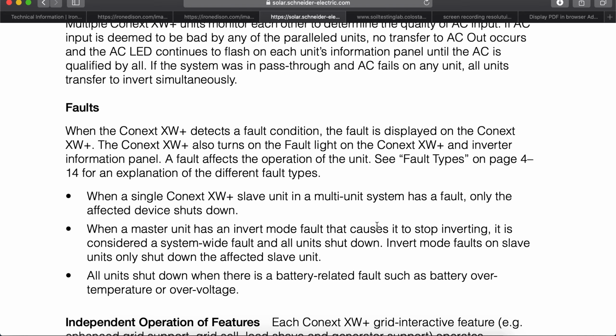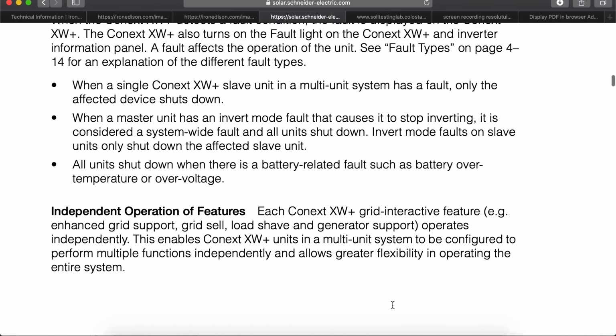When a single Conext XW Plus unit in a multi-unit system has a fault, only the affected device shuts down. When a master or leader unit has an invert mode fault that causes it to stop inverting, it is considered a system-wide fault and all units shut down. Invert mode faults on all follower units only shut down the affected follower unit. All units shut down when there is a battery-related fault, such as battery overtemp or overvoltage.